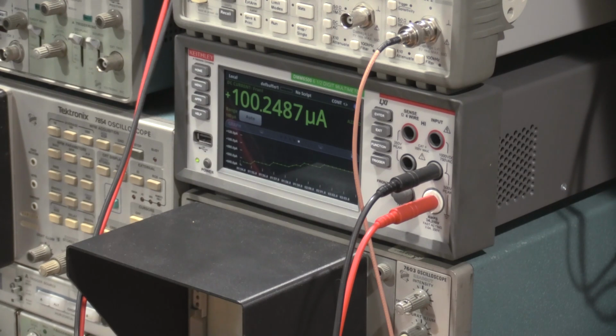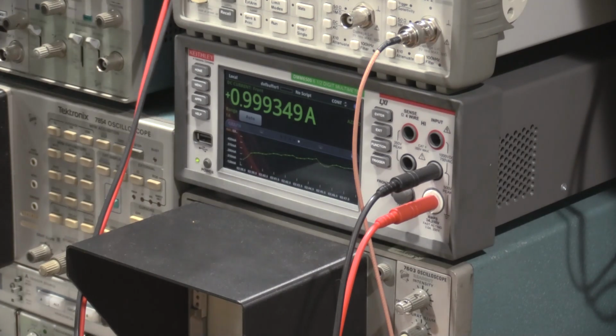So there's 100 microamps full scale, 1 milliamp, 3 nines, 10 milliamp, 100 milliamp. I'm just kicking it to standby now between ranges because as I was pushing the range switch, I saw the compliance voltage peak out for a second. And back to our 1 amp range. Not unhappy with that at all. I can't ask for anything better.